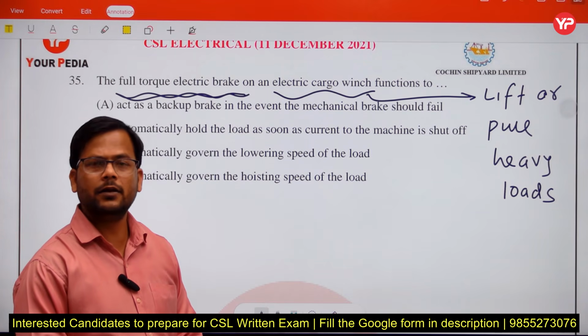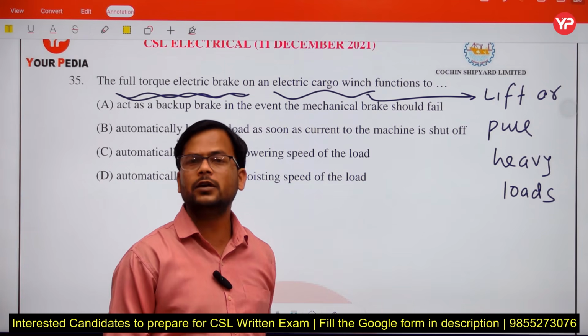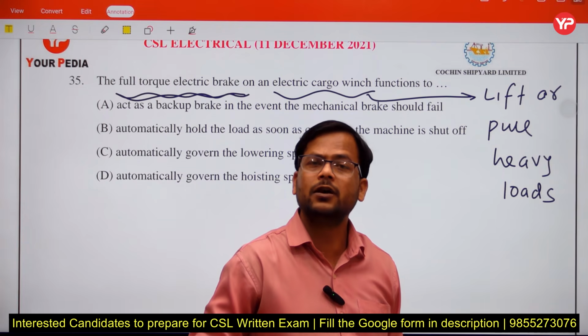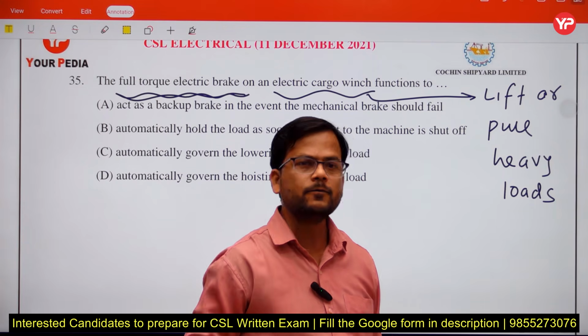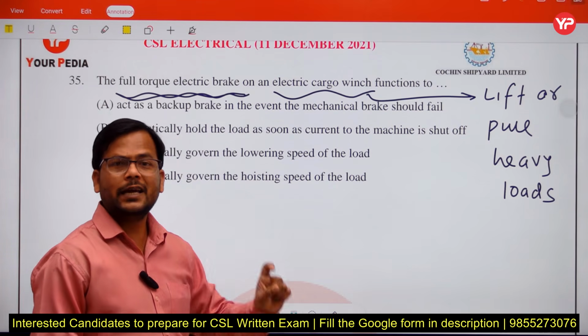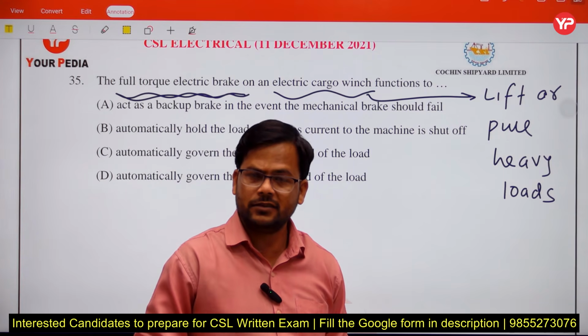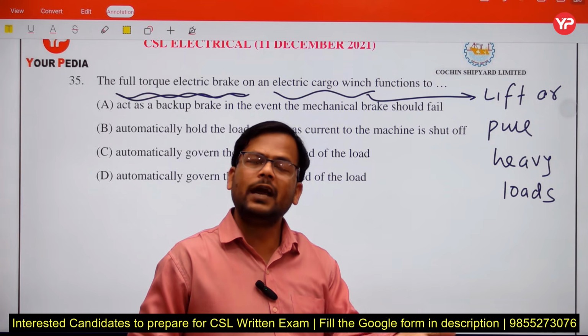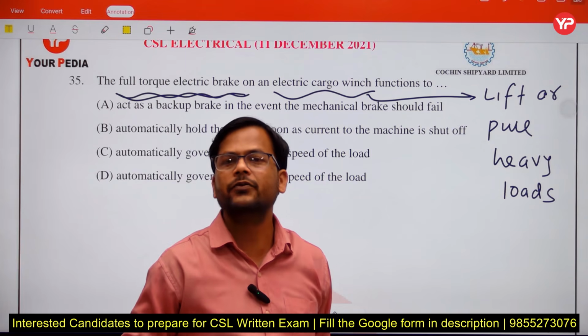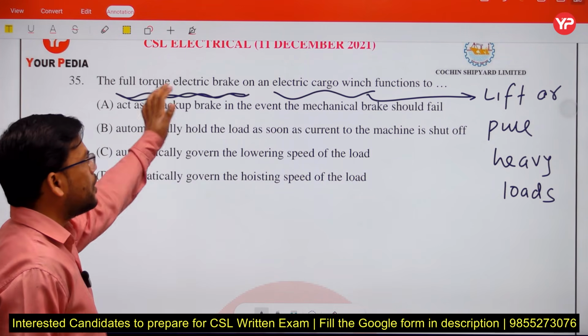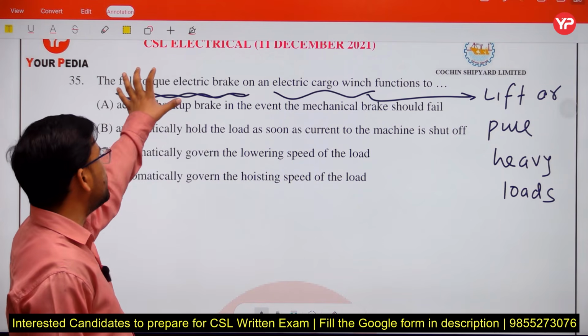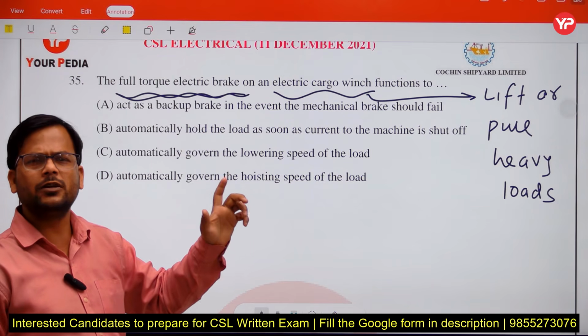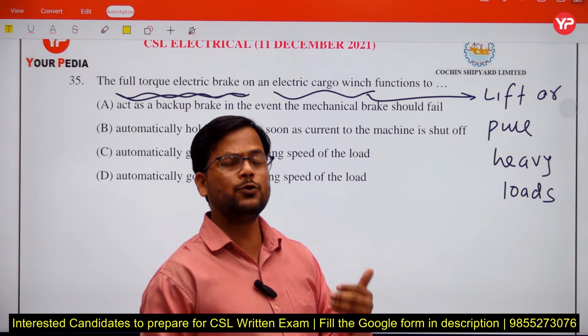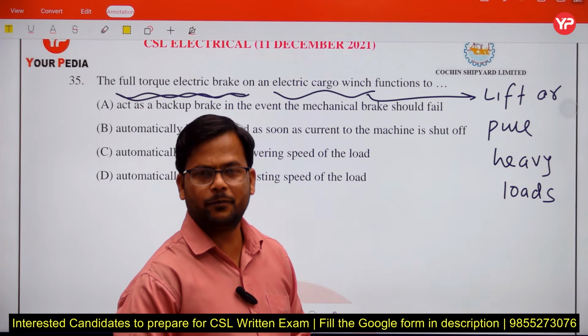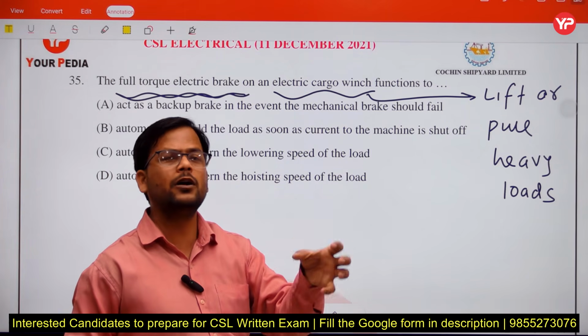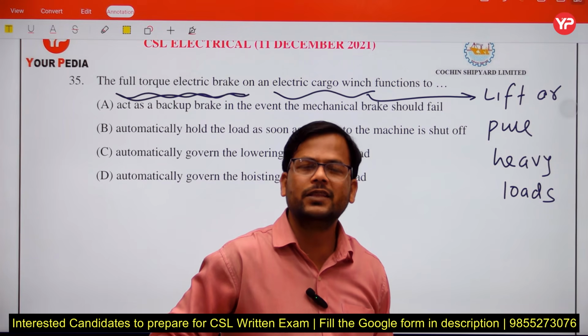But if the current supplied to the electric cargo winch is stopped, meaning current is zero, the full torque electric brake electromagnet de-energizes, and this brake grips the load at the position where it is present. So when current is flowing, the brake is released and not connected to the load, but when current reduces to zero by any means, the brake applies to the load and holds it in place.